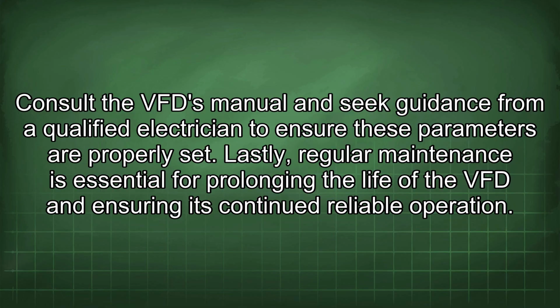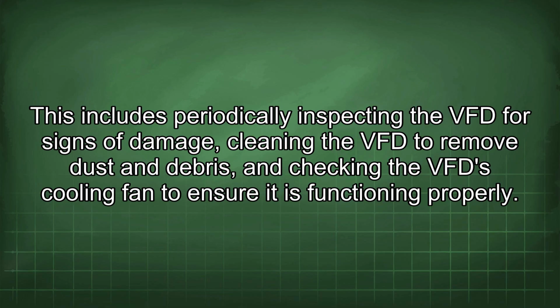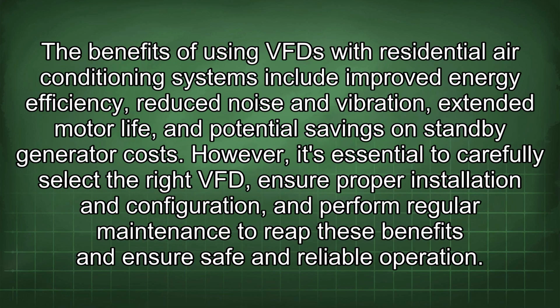Lastly, regular maintenance is essential for prolonging the life of the VFD and ensuring its continued reliable operation. This includes periodically inspecting the VFD for signs of damage, cleaning the VFD to remove dust and debris, and checking the VFD cooling fan to ensure it is functioning properly. The benefits of using VFDs with residential air conditioning systems include improved energy efficiency, reduced noise and vibration, extended motor life, and potential savings on standby generator costs. However, it's essential to carefully select the right VFD, ensure proper installation and configuration, and perform regular maintenance to reap these benefits and ensure safe and reliable operation.